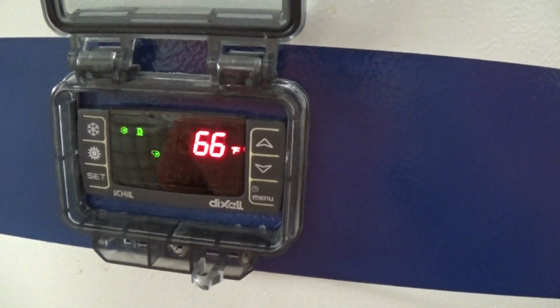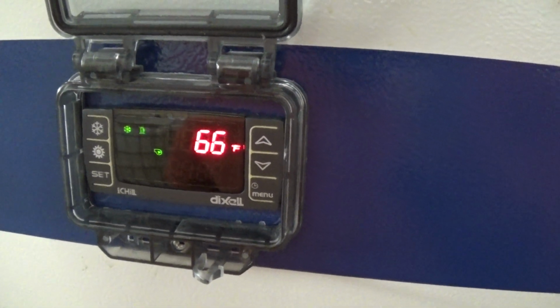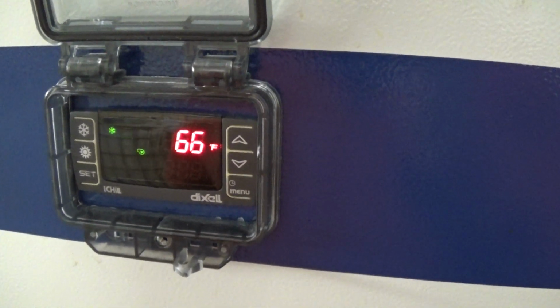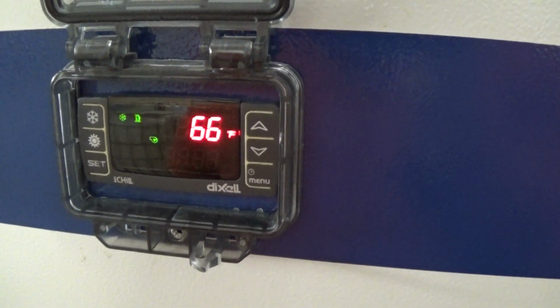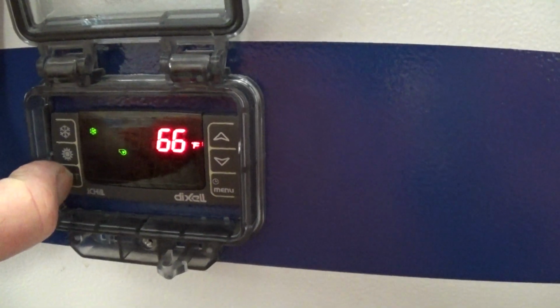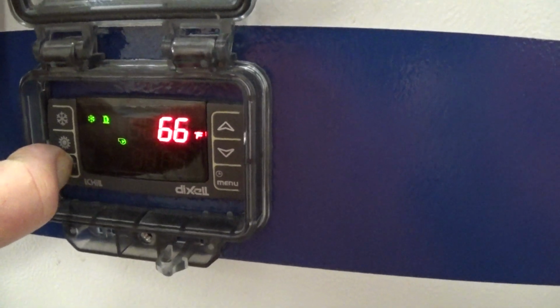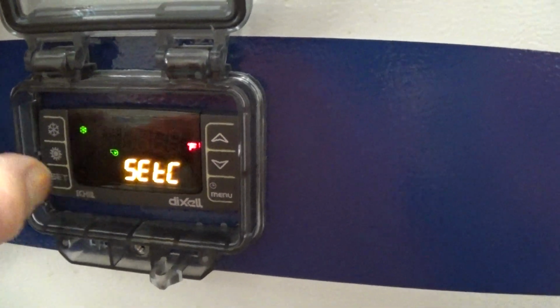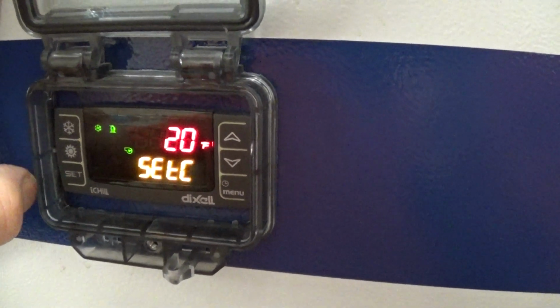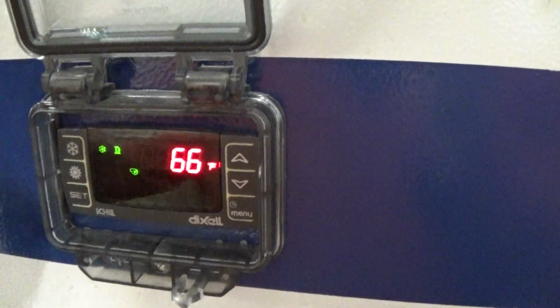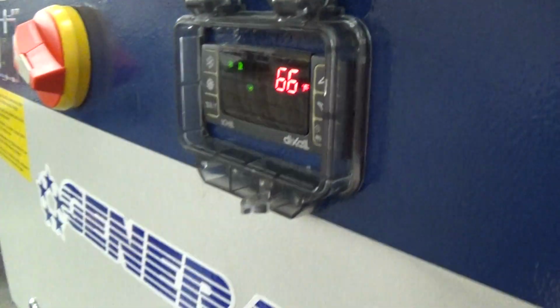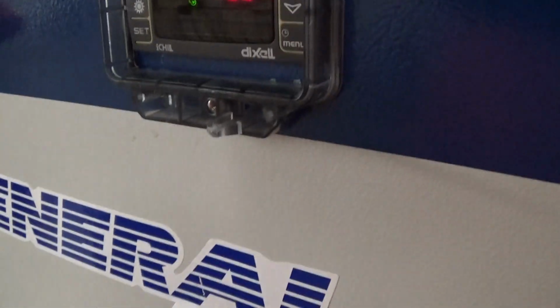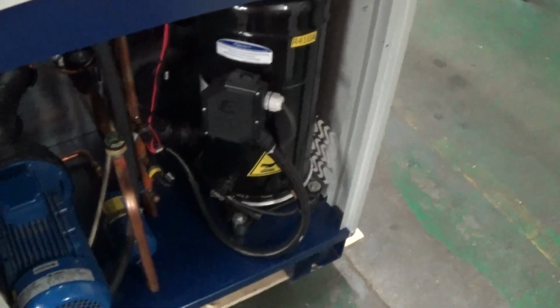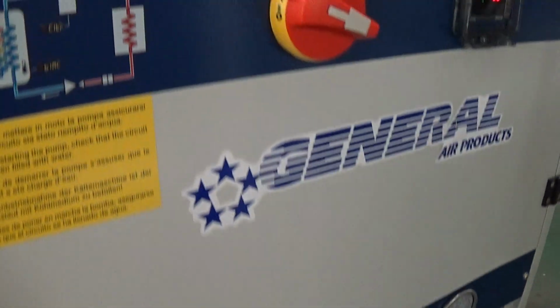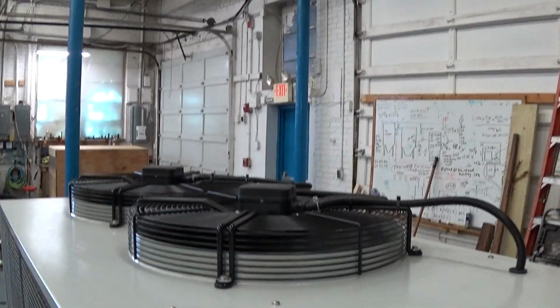And the compressor should turn on shortly after a little bit of a delay. But again, just to make sure that it's embedded and saved in there, I'm going to press that set button again. And that's telling me what my set point is, so it was saved. That's the initial scroll compressor noise when it first turns on, which is normal for a scroll compressor. It's starting to chill. The pump always runs, by the way, the glycol pump. Both fans are on.